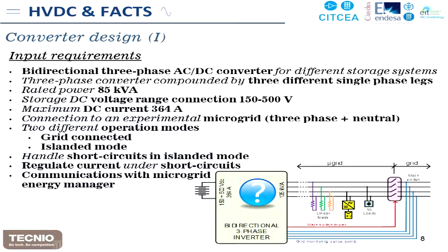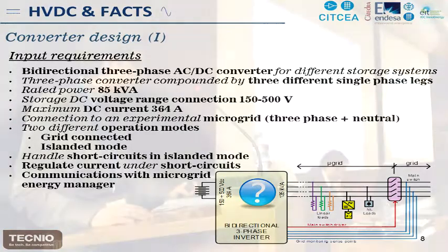Basically, we want to design a bidirectional three-phase AC-DC converter that allows operation with different storage systems, mainly batteries, but for different technologies. For the rated power, we have decided to design a converter of near 90 kVA, but with an overload capability of 50%.